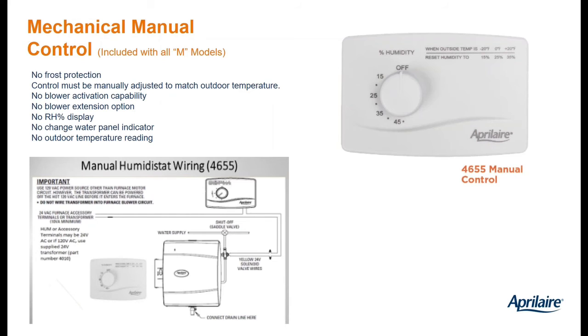That takes more time. You don't get the digital readout. You don't get the automatic adjustment. You don't get the simple, consistent, every-job-has-the-same wiring. You don't get the blower activation. You don't get the digital display of the RH. You don't get the indicator that it's time to change the water panel. And you don't get the easy troubleshooting option of the error codes being displayed. So I think that automatic humidification has a lot of advantages over the manual humidistat. It makes a lot of sense to consider switching if you don't already. And as always, our tech support group is happy to answer any questions you have, or your AprilAire district sales manager would be happy to do a training class or just talk to you about the advantages.